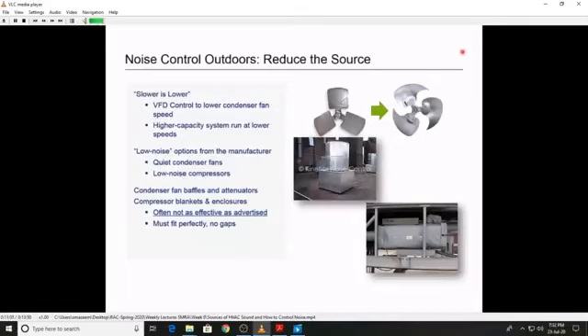So let's say you can add a VFD control to lower your condenser fan speeds, so that if you're not demanding absolutely maximum full cooling capacity at any other time, everything can slow down and thus quiet down. And in general, higher capacity systems can be spec'd and run at slightly lower speeds. You can look into low noise options from your manufacturers, such as quieter condenser fans or low noise compressors. And typically they come at a premium. There is often a price associated with that.